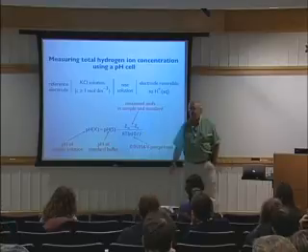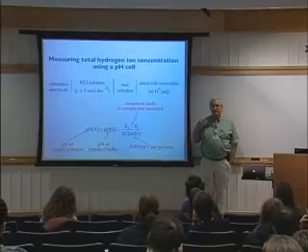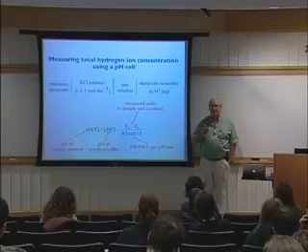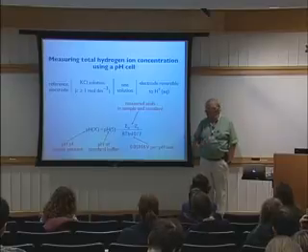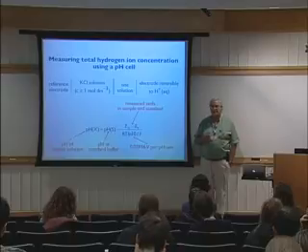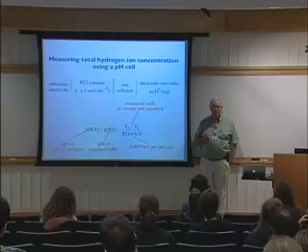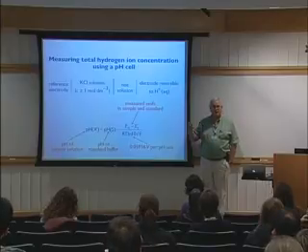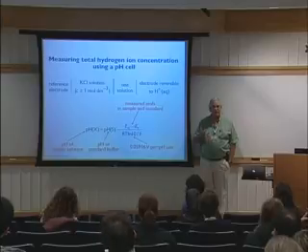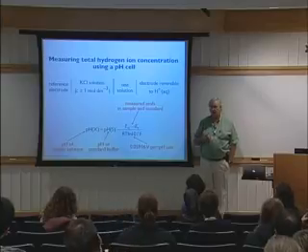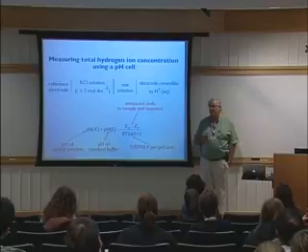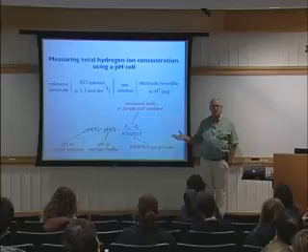This term on the bottom is, as I said, the amount of voltage change you will get for a factor of 10 change in pH. It's not much. It's about 60 millivolts. So that's for 1 pH unit. So for 0.01 pH units, it's going to be 0.6 millivolts. This is arithmetic you can follow sensibly. So you have to have a pretty good pH meter to get reasonable pH measurements.